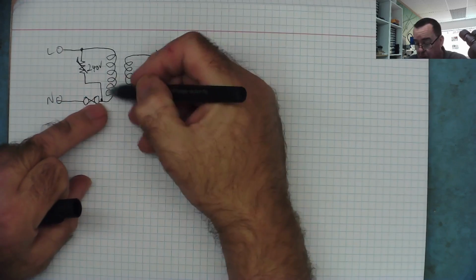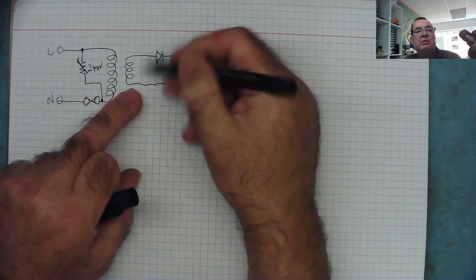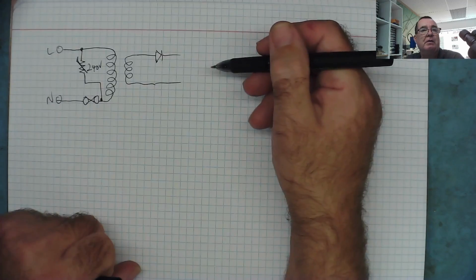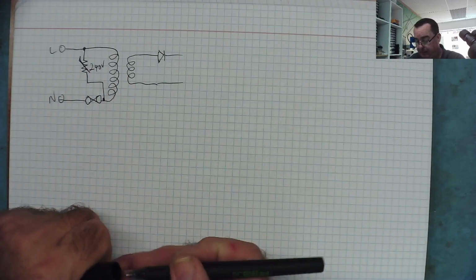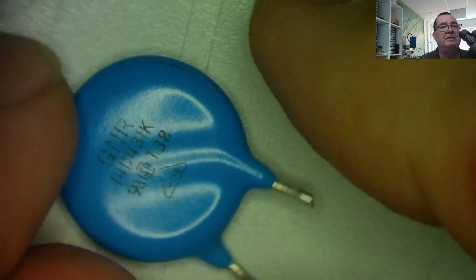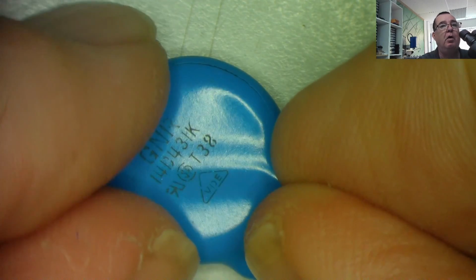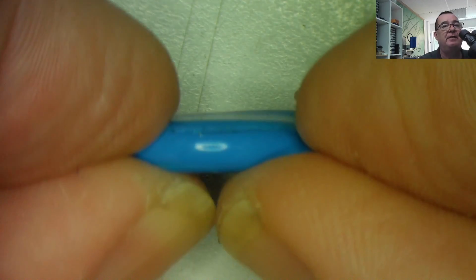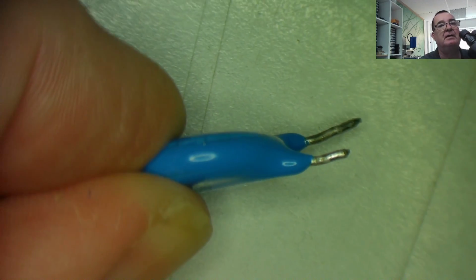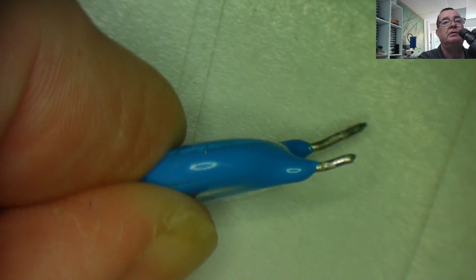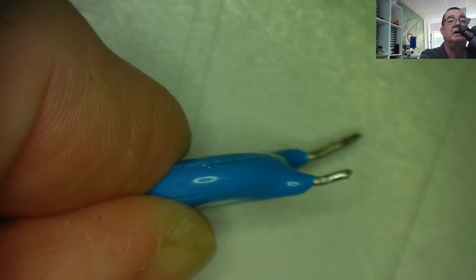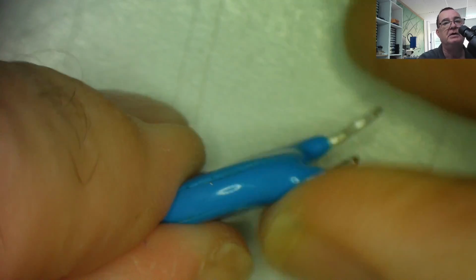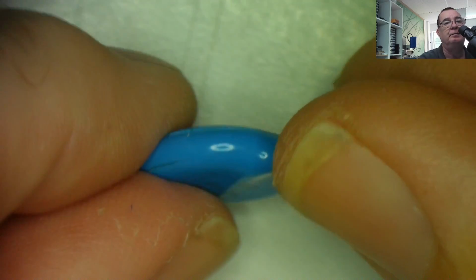So if you get a voltage spike here, or induce a voltage spike into here, which will go into the low voltage circuit, that's what the thing is for. When these fail, they normally blow up, and in our case, it has actually failed. Can you see where it's split down the side there? Let's get the focus on it a little better. Yeah, you can see it. So this is what happens to them, usually a bit more spectacular than this, but you can see it's cracked, it's broken, it's blown, yeah?